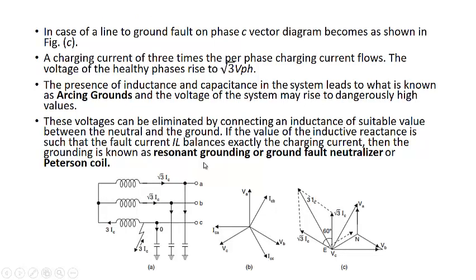But in this case, you will see that this is root 3 IC, because the voltage across this capacitor will now be the line voltage, so the current will also be multiplied by root 3. The total current, that is the fault current, we can see in this case is 3 times IC. It is because of the summation of this current and this current that will flow through this and then back through this winding of the generator. So this is how this can be done.